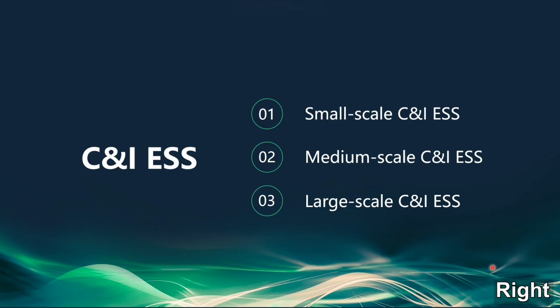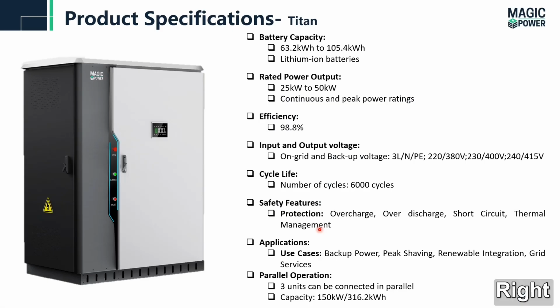So we have divided the commercial and industrial energy storage system into three parts: small scale, medium scale, and large scale. Basically, there are three standard energy storage systems for Magic Power, and we will learn them one by one. The small scale is the series called Titan. The battery capacity ranges from 63 to 105. The battery technology is lithium ion. Rated output power is from 25 to 50, which is a continuous and peak power rating. The efficiency of the system is 98.8%, and the input and output voltages, depending on the grid standard, could be 380, 400, or 415, because these systems are three phase.